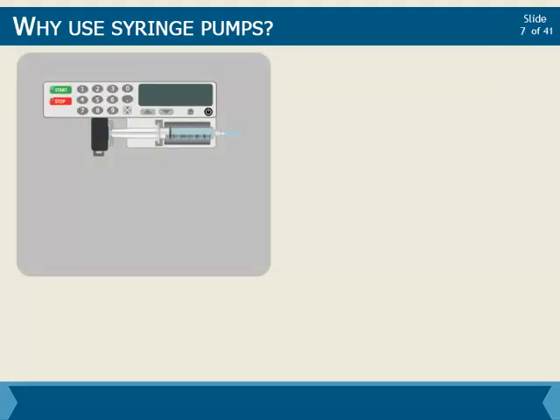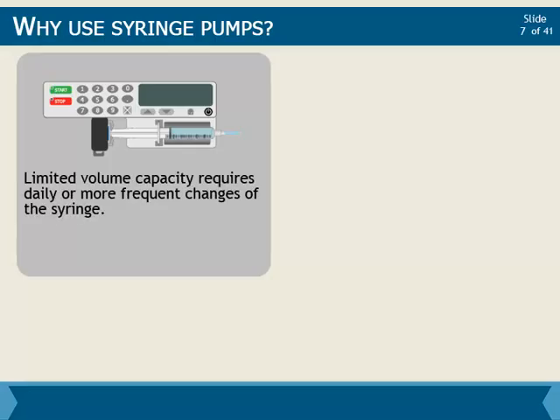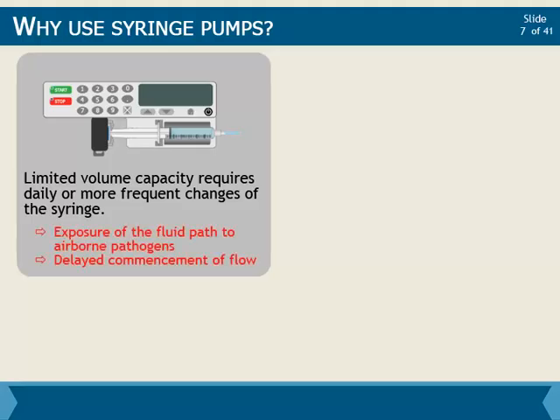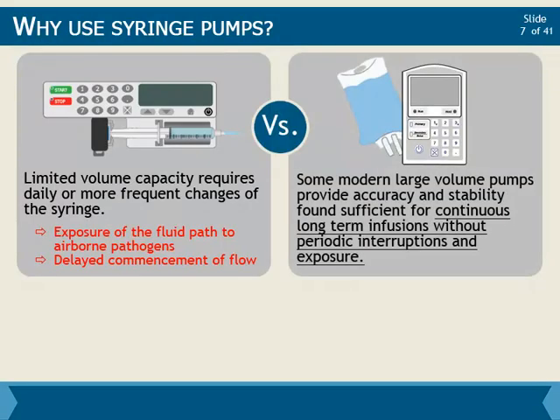While syringe pumps have historically been used for delivery of short half-life, continuous medications, their limited volume capacity requires daily or more frequent changes of the syringe. This repeated action poses several significant unwanted effects, including exposure of the fluid path to airborne pathogens and delayed commencement of flow. The design of some modern large-volume pumps provide accuracy and stability found sufficient for continuous long-term infusions without periodic interruptions and exposure.